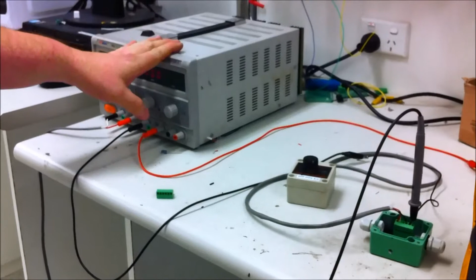I'll turn the load cell simulator up now to what I've calculated those 3-ton load cells should put out. And you can see now we've got 14 milliamps of loop current, which isn't enough for that receiver to calibrate.